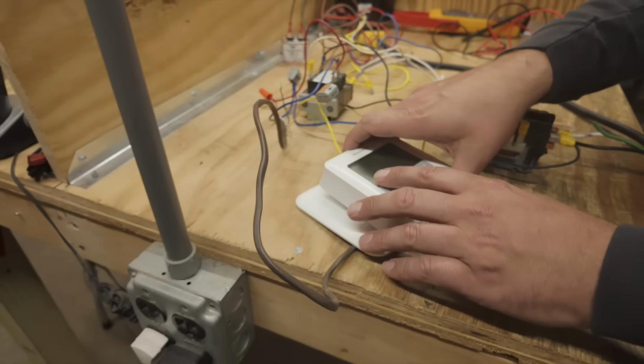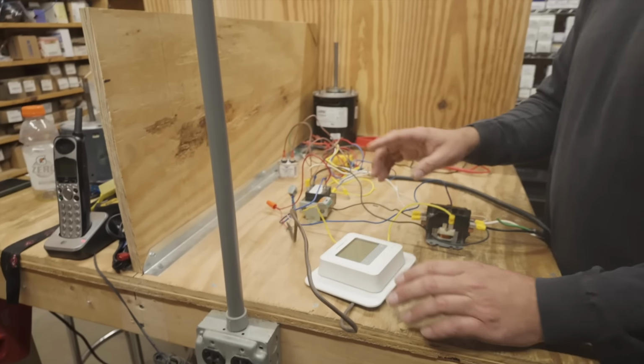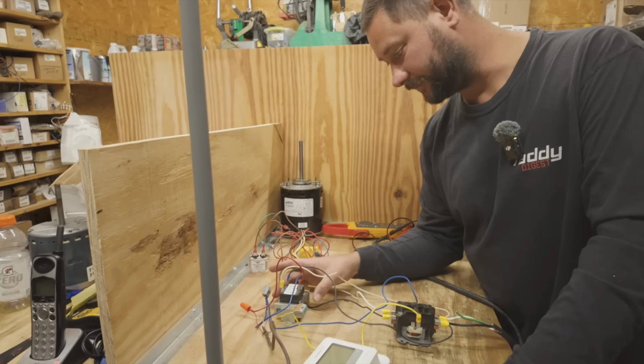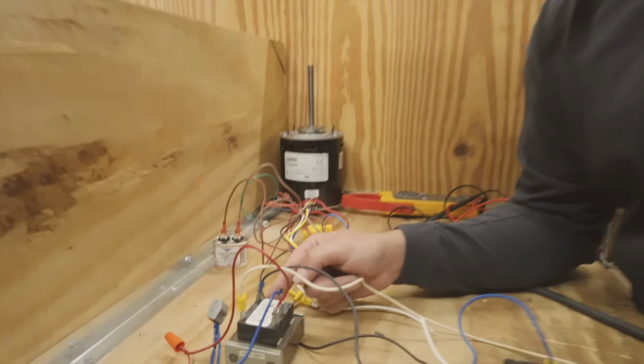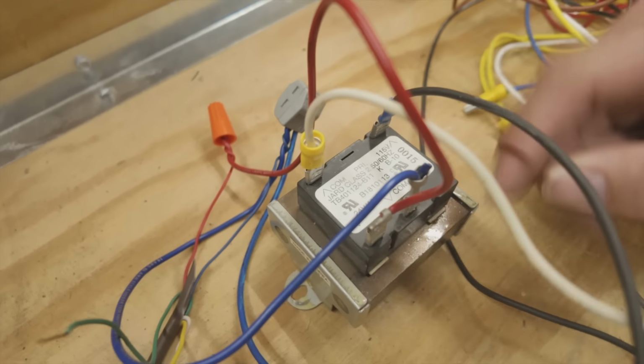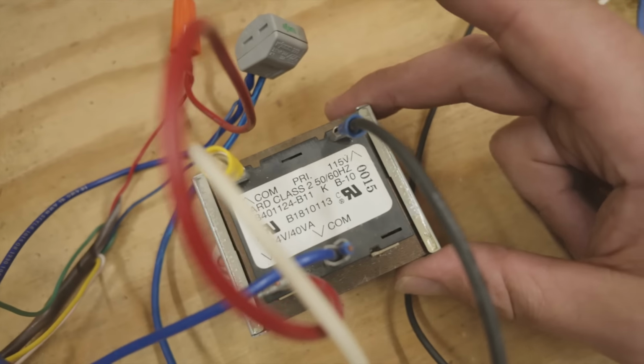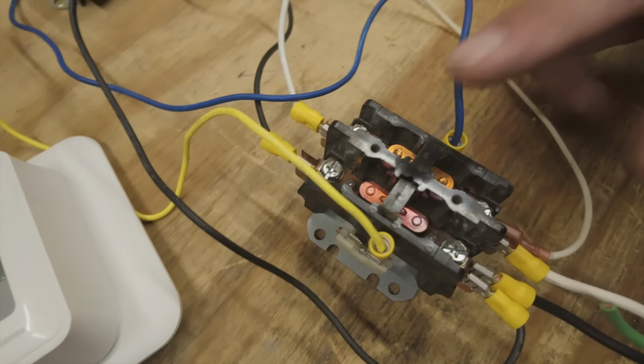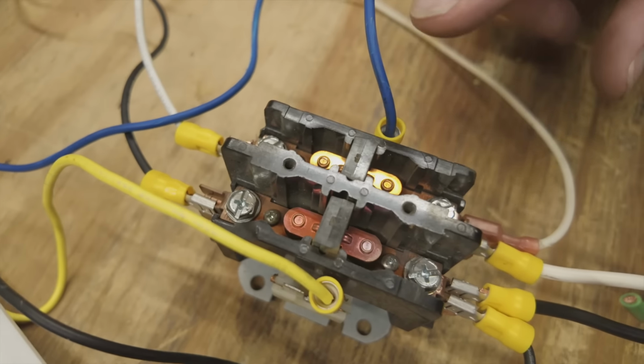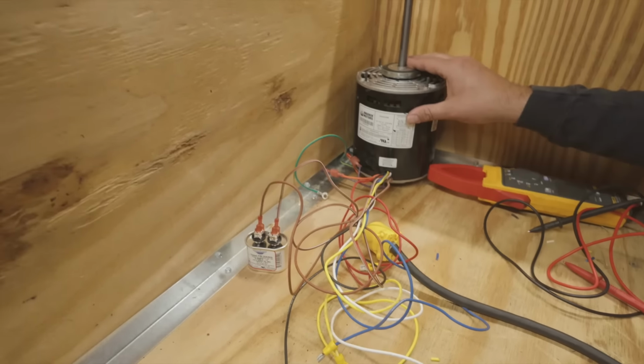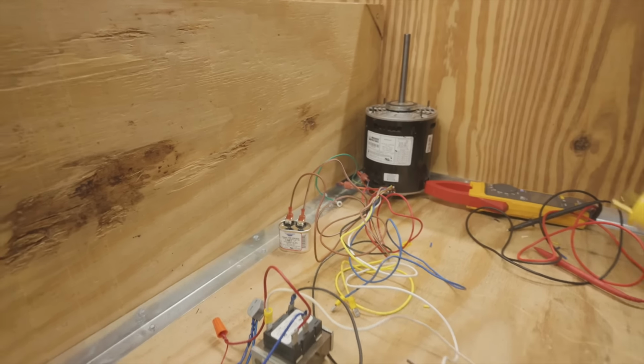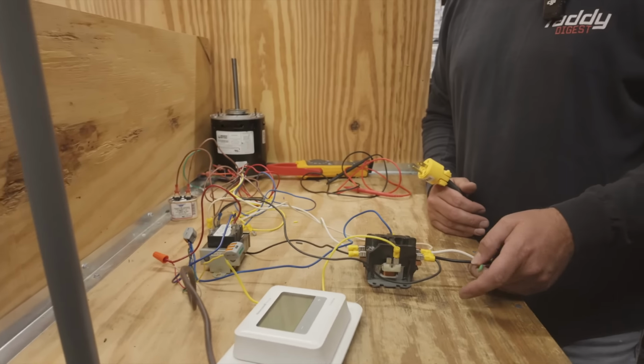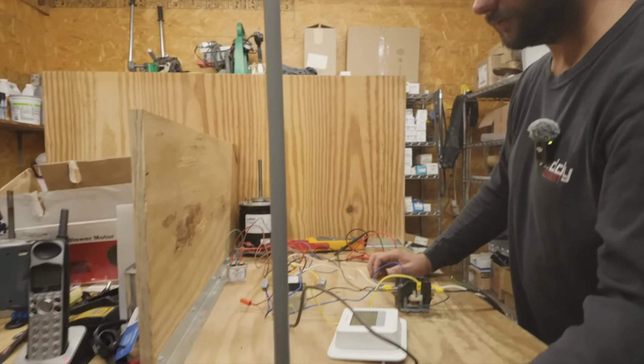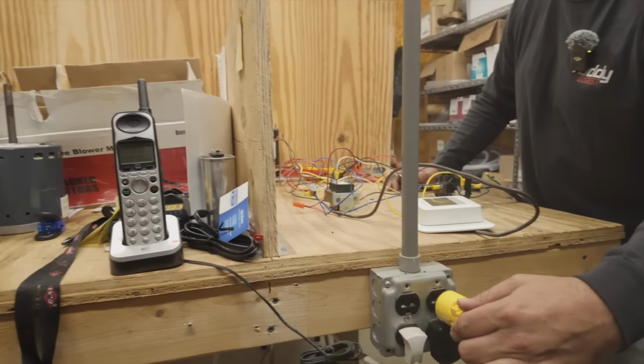I'm going to place my thermostat over the back plate. I've also got a transformer here, which is 115 volt to 24 volt. This is a step-down transformer. I've got a contactor right here, which is the first type of relay that we're going to be using to power our 115 volt fan motor. And I've got power going to this contactor right on the line side. So first thing we're going to do, plug it in.